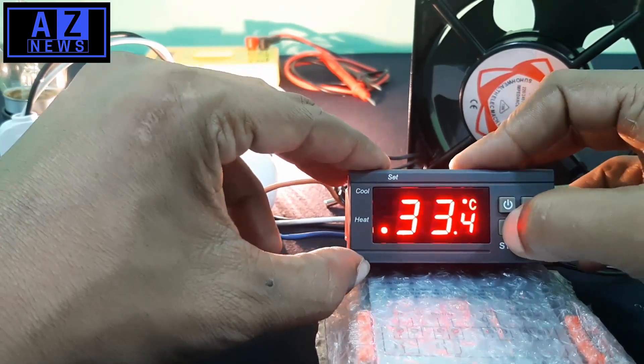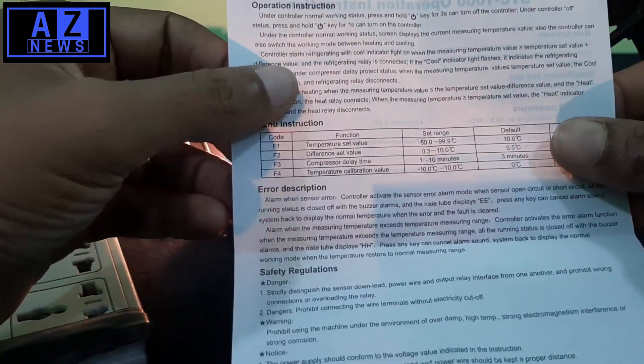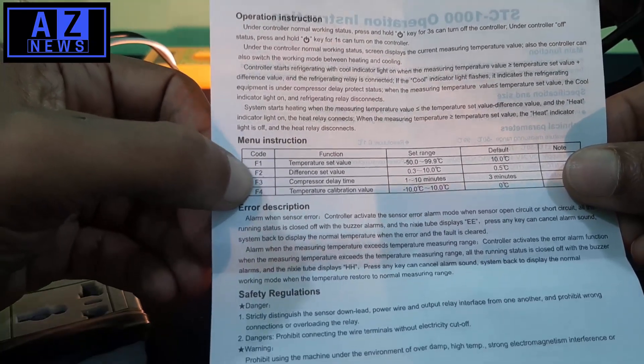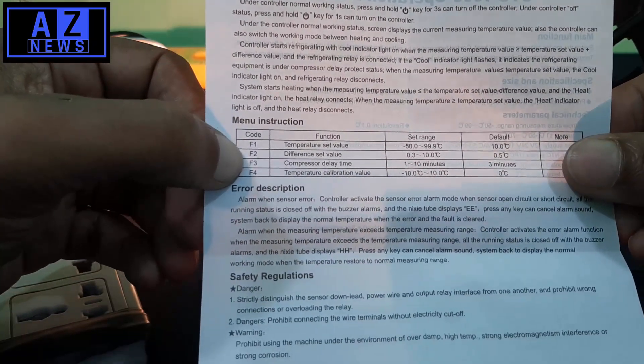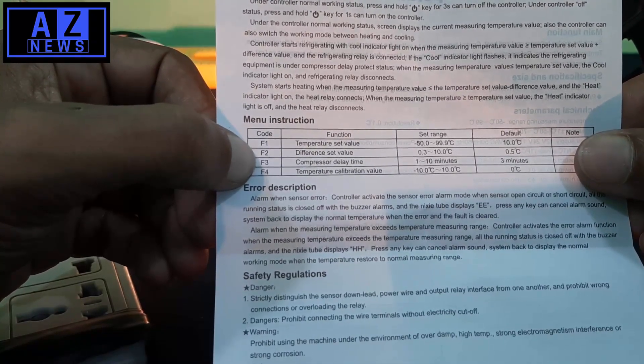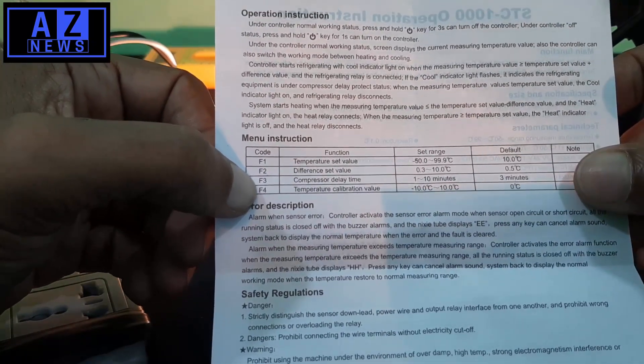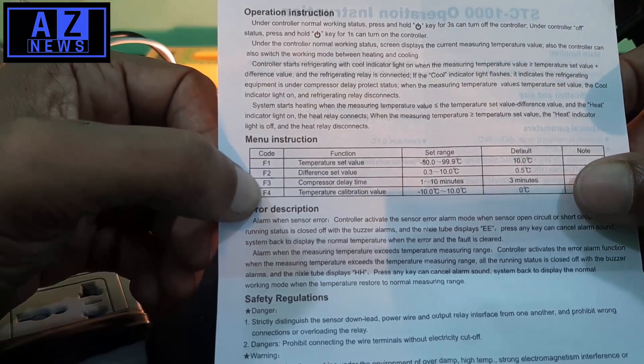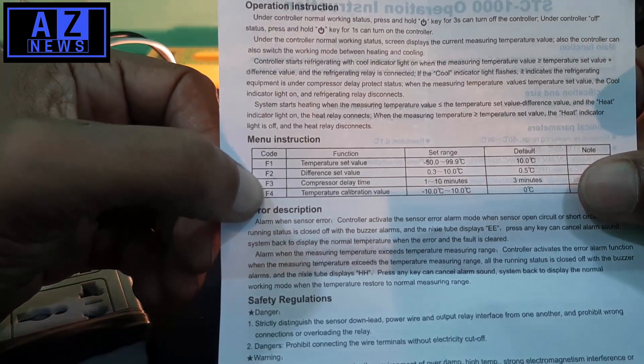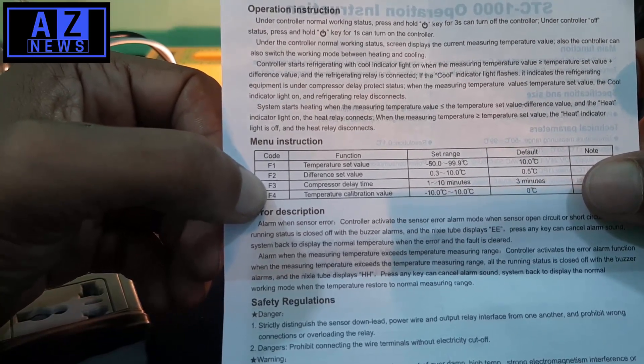There are two more functions you should know about: F3 and F4. F3 is the compressor delay time — that means how much time it will delay before turning the output on and off. F4 is the temperature calibration value, which is minus 10 to plus 10 degrees centigrade, so you can calibrate the temperature reading if needed.